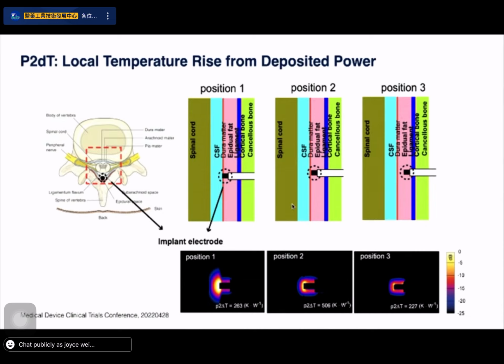Now for this, I would first construct and calculate the deposited power that's caused by this, and then I do the thermal simulation assessment of this, which results in this power to temperature conversion factor. And if we look at the different positions and the thermal conversion factor, depending on where it's placed, this factor can be much larger or much lower. So we see in position 2, for example, where there's only a slight offset of the tip between the tissue boundaries, the conversion factor is 506 Kelvin per watt, which is much larger than for some of the other cases that we test.